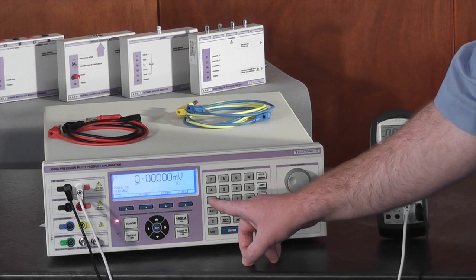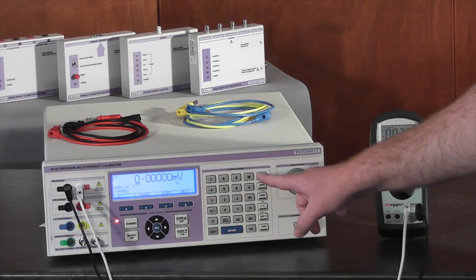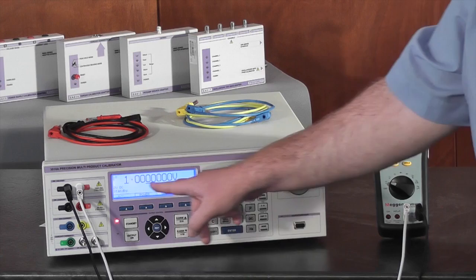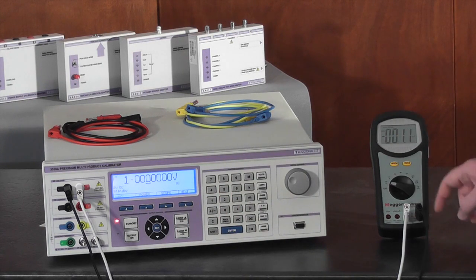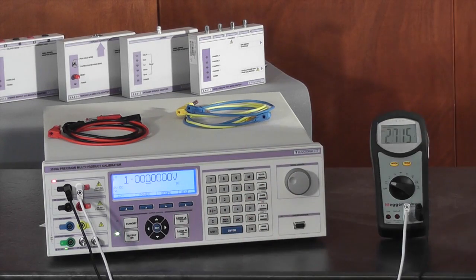To enter 1 volt on the calibrator, simply press the 1 key followed by the volts function key. Pressing enter will make the required value display on the main display. After ensuring your connections are correct, press the output on key.